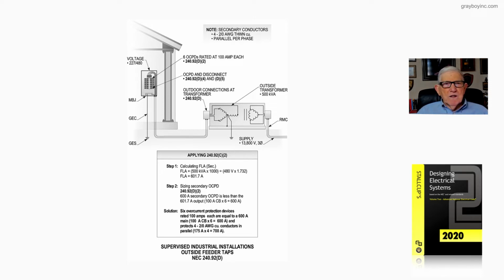And then, of course, we have 6 mains at 100 amps that would protect it, or we'd have 1 main at 600 amps. But we're protecting the output of the transformer plus the conductors. Now, this is what you must remember.